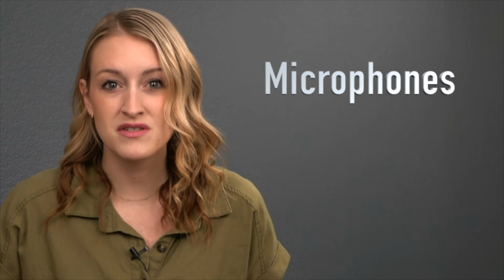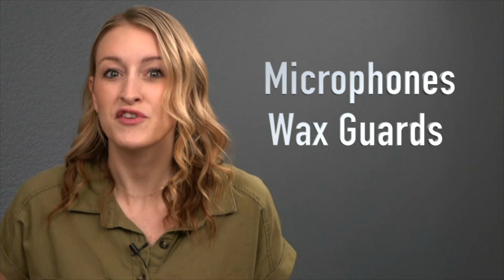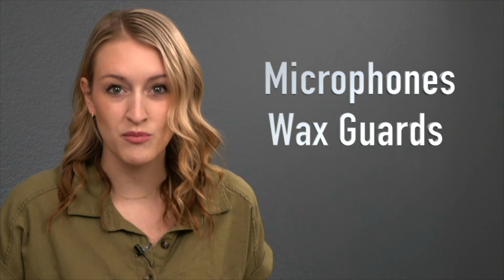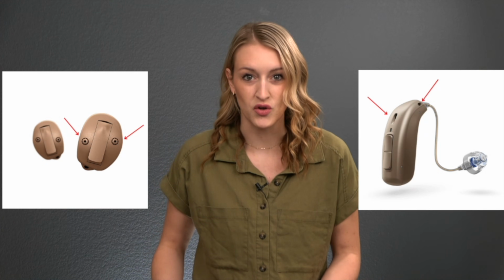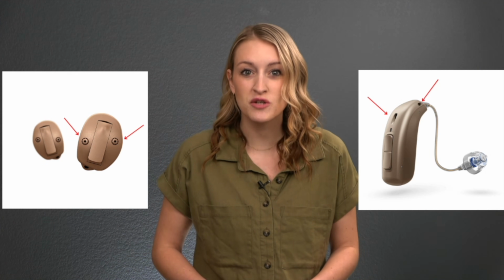There are 3 main parts of a hearing aid that require routine maintenance: the microphones, the wax guards, and if you have a custom hearing aid or custom ear mold, the vents. The location of your hearing aid microphones will depend on the make and model, but these microphones should be cleaned weekly. This can be done with small hearing aid brushes or can be done with a soft bristle toothbrush. Just make sure that you label it appropriately as hearing aids only.